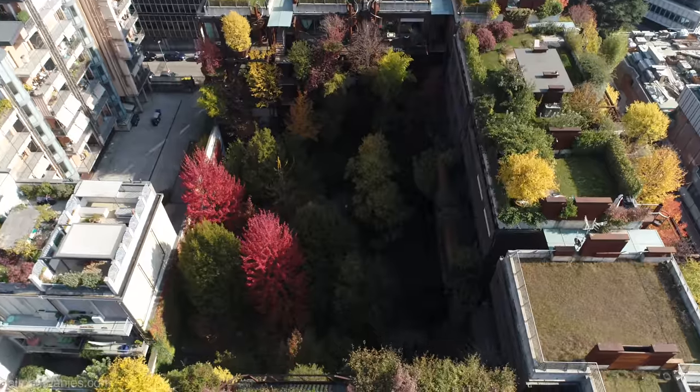But the interesting side of this plant is especially during the summer. During the summer, the heat pump produces at the same time hot water for domestic hot water production and also cooled water. The cooled water goes to the flats for space cooling and the hot water for domestic hot water production. That means that it's a kind of floating system that takes hot energy from the space cooling and puts this hot energy to the domestic hot water production without using water from the underground. That means that with 1 kilowatt hour of electric energy, we can produce approximately 8 kilowatt hours of useful energy.